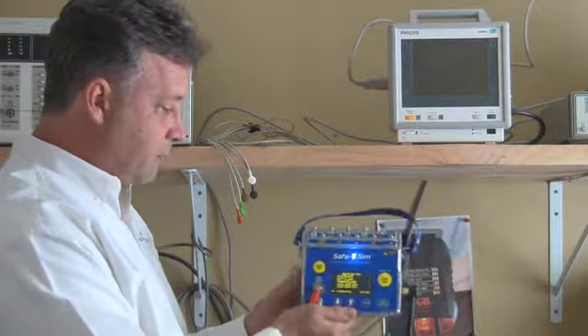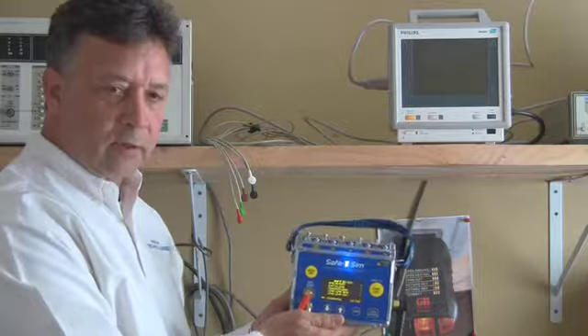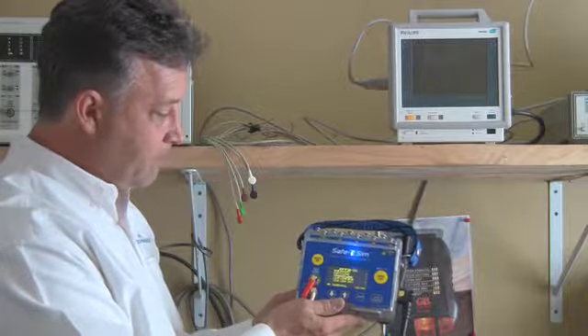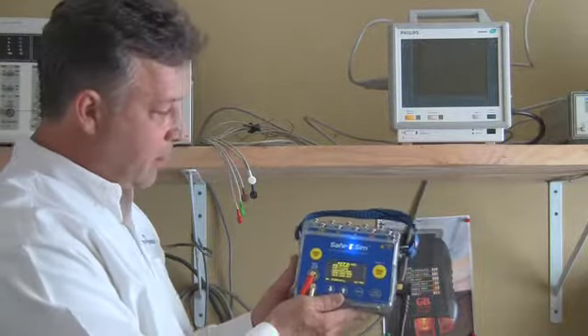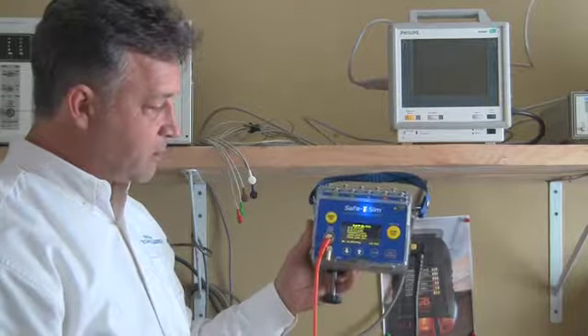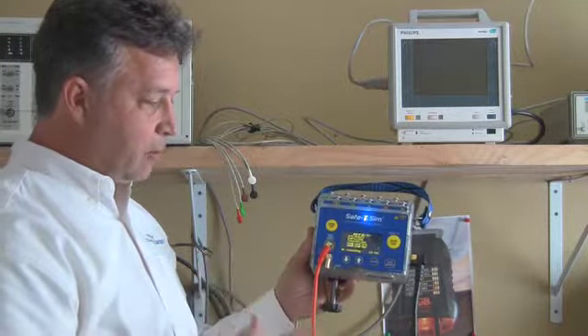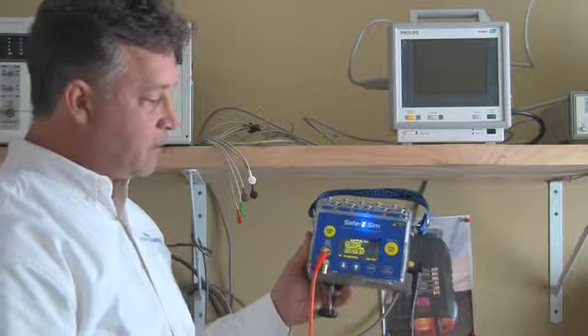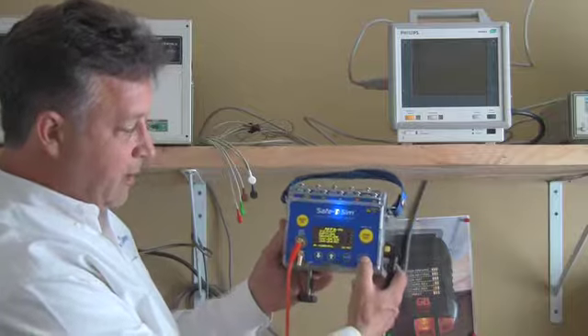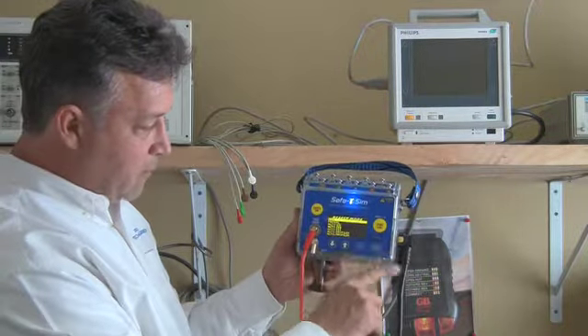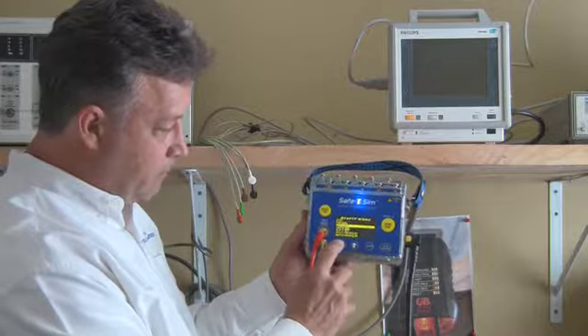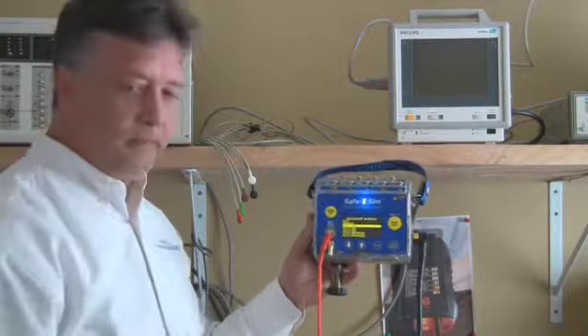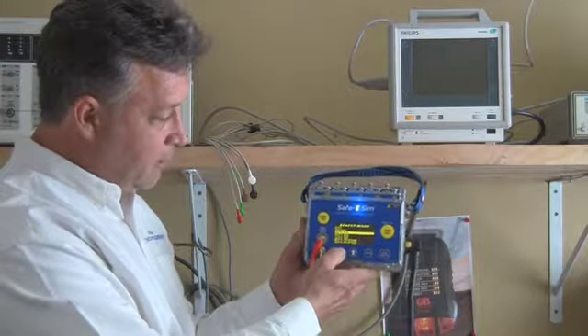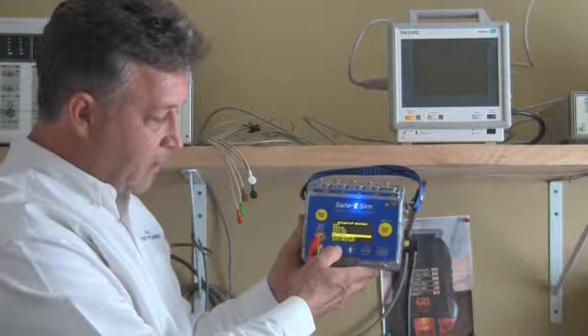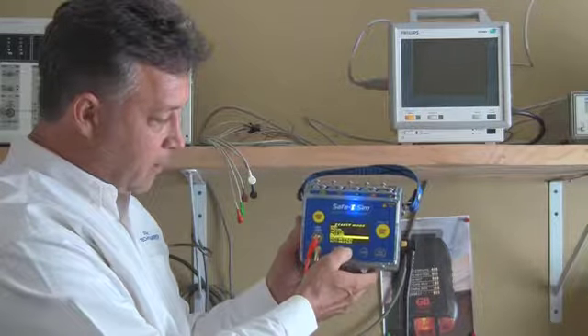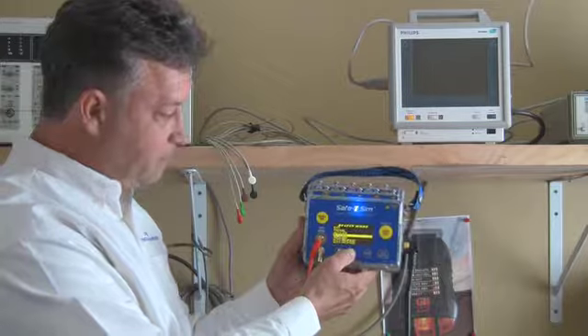We really focused on making it as small as the smallest handheld electrical safety testers around, but as smart as the bigger boxes that are very expensive, in terms of making it capable of doing automated testing defined by the user. So if I hit the auto manual button here, you'll see what I mean. You can select the mode from this screen. You've got manual mode, which is very straightforward, and then you've got up to 5 automated profiles that you can define. Once you've set those up, you don't have to touch them again. They'll be there for you when you need them, and you can select the different profiles from this screen.